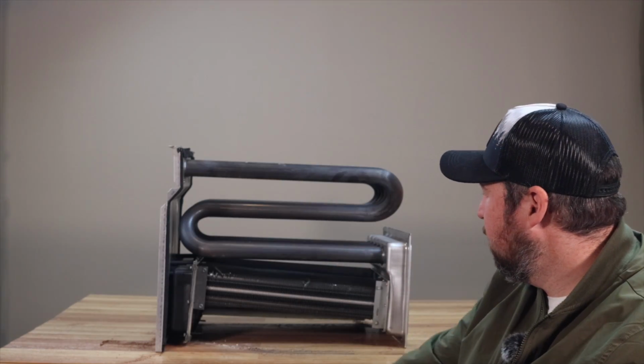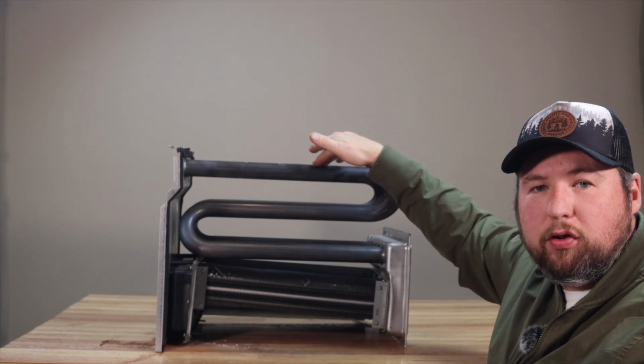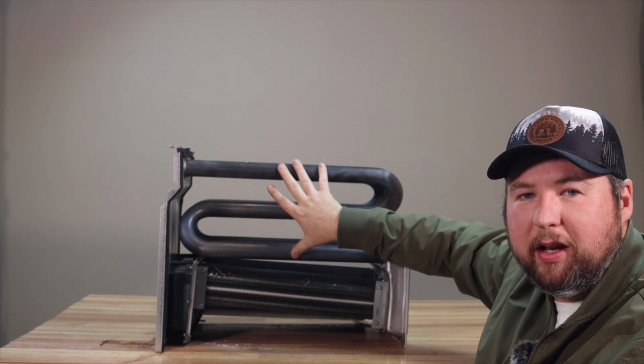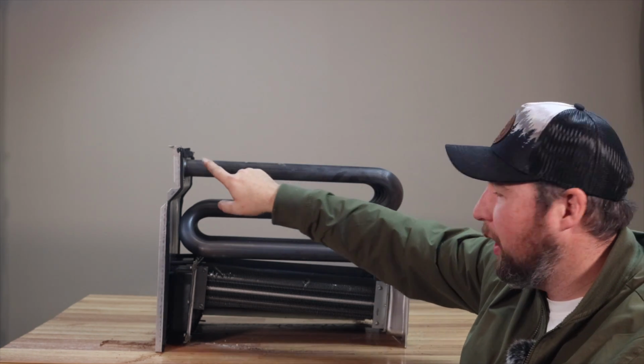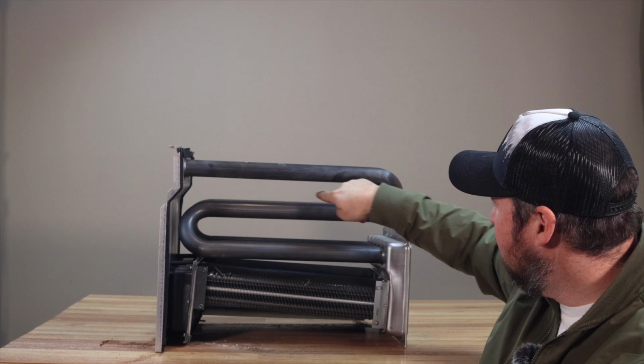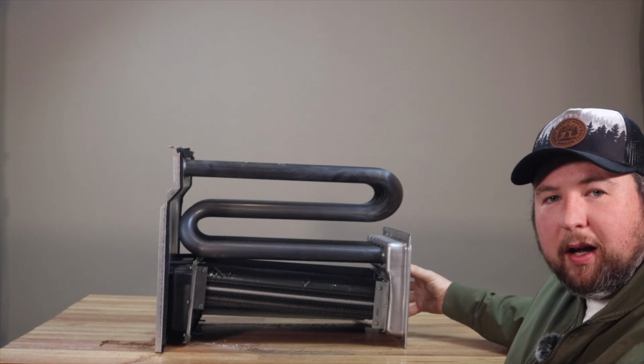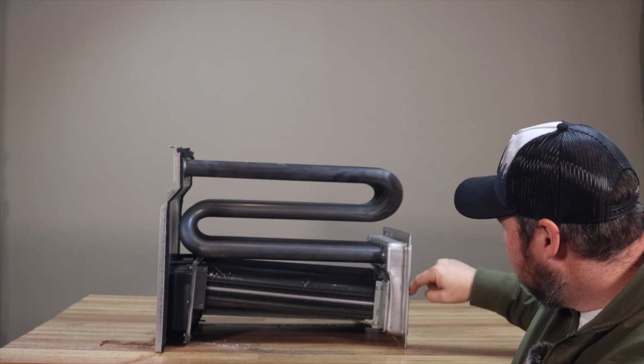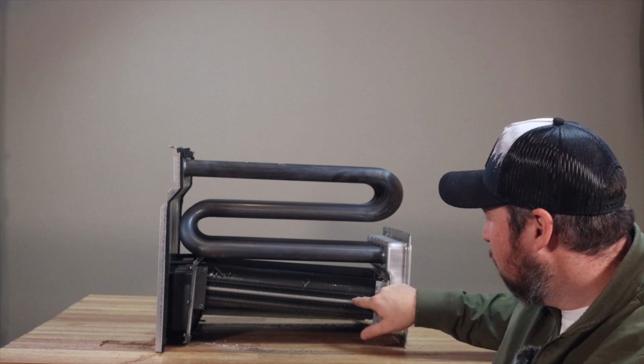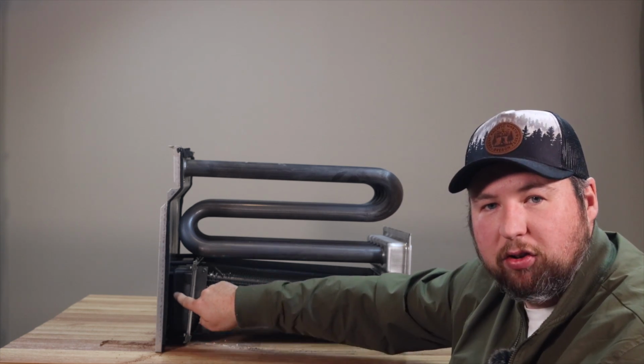So this right here is also a 90% heat exchanger, but this is a tubular style. So you have your primary heat exchanger, which is your standard tubes, right? Your combustion chamber here snakes through, goes into this transfer box in the back, transfers it over to the secondary heat exchanger, runs through the tubes, and then you have the water collection box here.